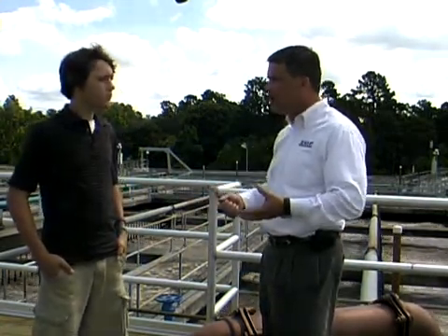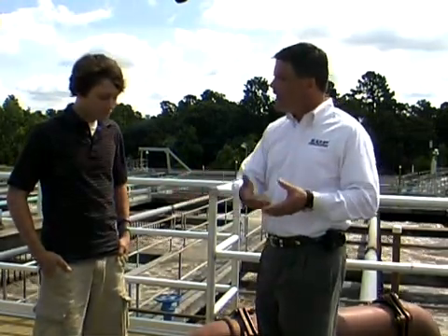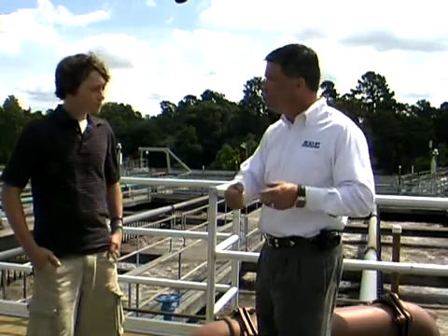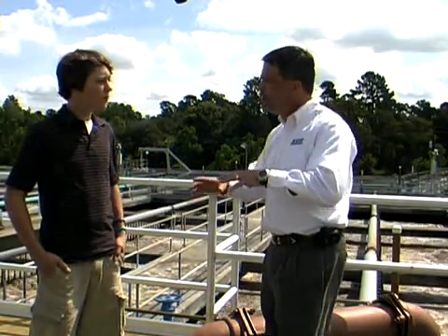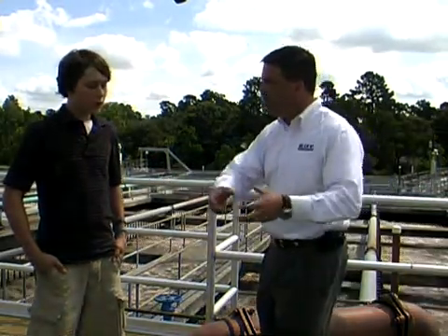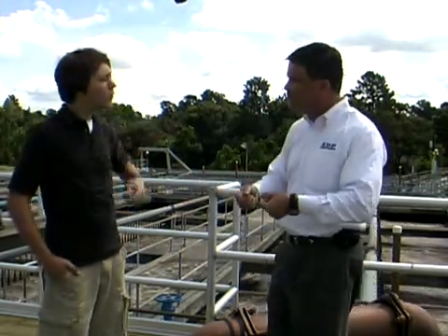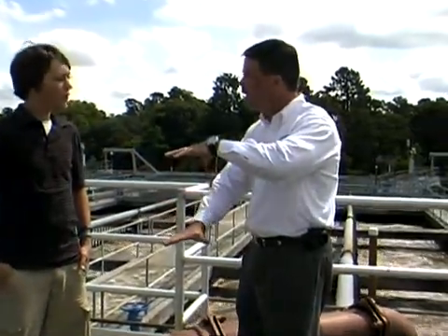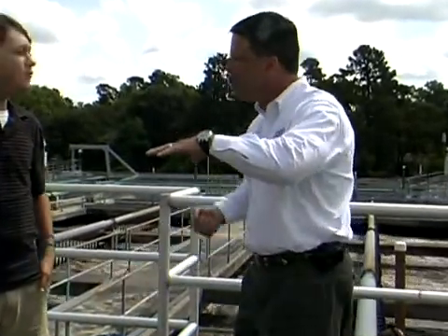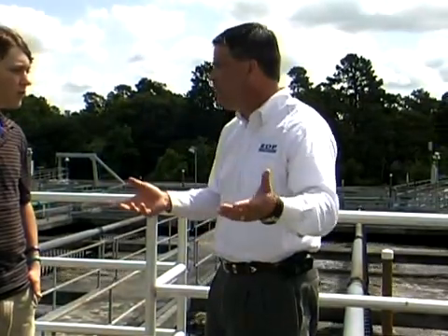The organics are dissolved in the water, and it's very difficult to remove them from the water by processes that are economically feasible. So we have the bacteria attack those organics in the water, use them as a food source, and grow more bacteria, because the bacteria are slightly heavier than the water. So what I do is I convert all this organic material into more bacteria. Bacteria is heavier than the water, so then I take that water with the bacteria in it and put it into a tank and let it settle. And the bacteria separate from the treated water. Well, it's easy to remove the bacteria from the bottom of the tank. Then the clear water that's left behind flows on to the next process, which is disinfection.